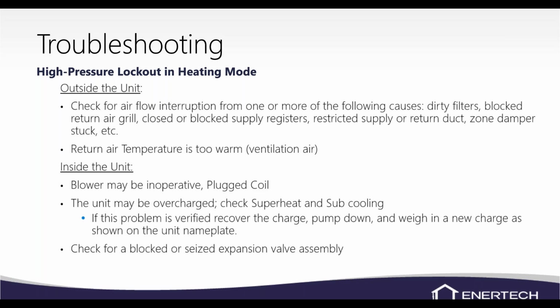Check for a blocked or a seized expansion valve. Normally, I don't see the high pressure lockout when the valve is stuck. But it occasionally will. It basically is going to pump the system down. You could have a high pressure switch issue or a board issue. So if you put your refrigerant gauges on there and the refrigerant pressures don't show a high pressure, then check the switch. And it could also be a board problem too.